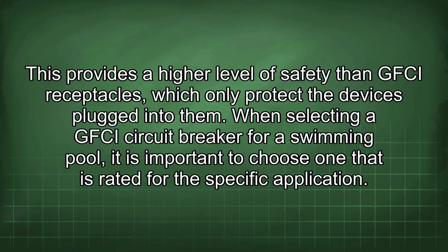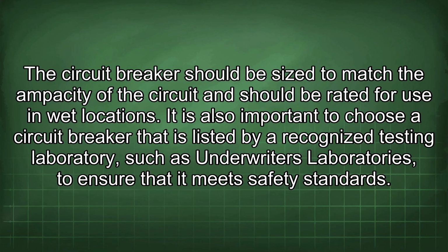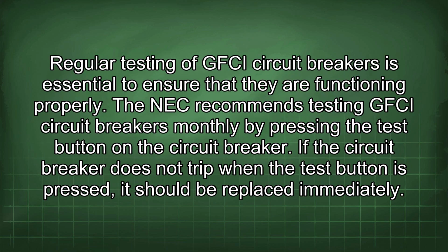When selecting a GFCI circuit breaker for a swimming pool, it is important to choose one that is rated for the specific application. The circuit breaker should be sized to match the ampacity of the circuit and should be rated for use in wet locations. It is also important to choose a circuit breaker that is listed by a recognized testing laboratory such as Underwriters Laboratories to ensure that it meets safety standards. Regular testing of GFCI circuit breakers is essential to ensure that they are functioning properly. The NEC recommends testing GFCI circuit breakers monthly by pressing the test button on the circuit breaker. If the circuit breaker does not trip when the test button is pressed, it should be replaced immediately.